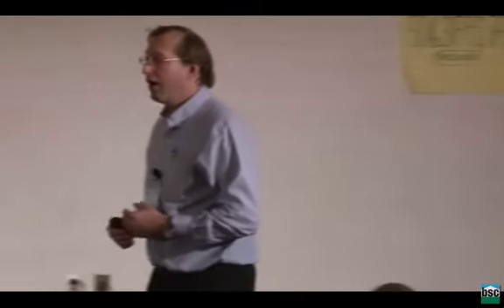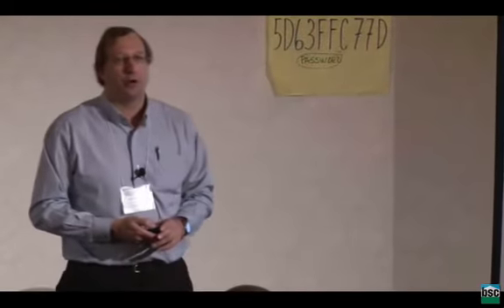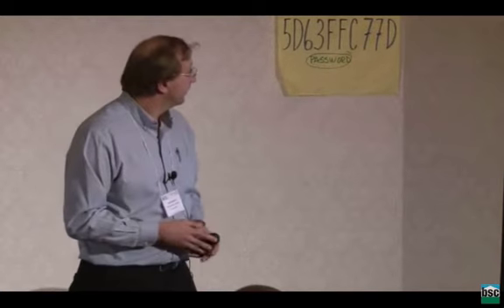So the technology problem with heat pumps, air source heat pumps to be clear, is not that we can't extract the heat out of 0 degree air or even minus 10 degree air, because there are York heat pumps that are rated down to minus 10. But it's that at higher than rated temperatures, they produce way too much performance. And this is back to the limitations of single speed technology. So you need to come up with a way to change the output in relationship to the need.